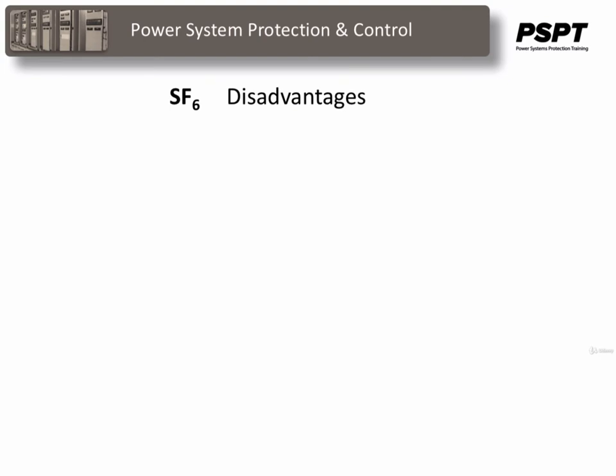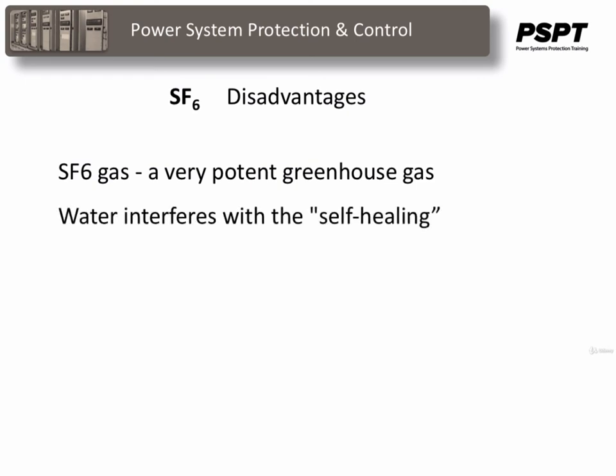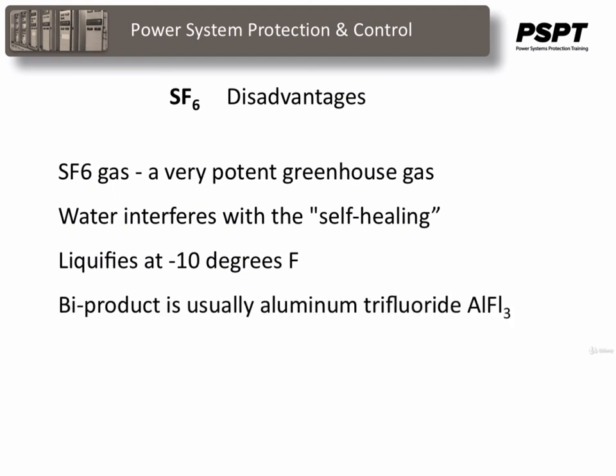Some of the disadvantages of SF6 gas are, one, it is a very potent greenhouse gas, and safety regulations are being introduced in many countries in order to prevent the release of this gas into the atmosphere. Water interferes with the self-healing properties, and therefore it must be kept very pure and very dry. This gas also liquefies at very low temperatures, below minus 10 degrees Fahrenheit. And a byproduct is usually aluminum trifluoride, which is a white powder that is acidic when combined with moisture and would add to the degradation of any equipment that comes in contact with it over a period of time.